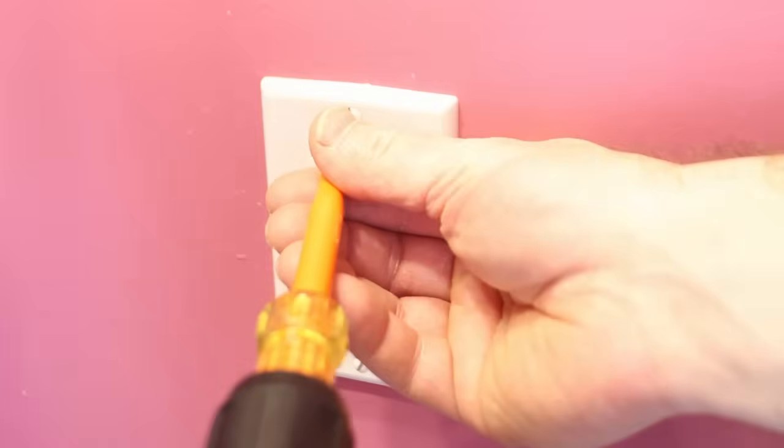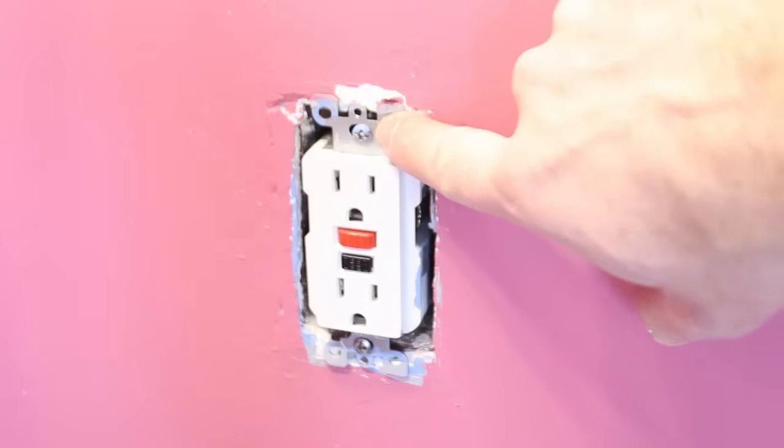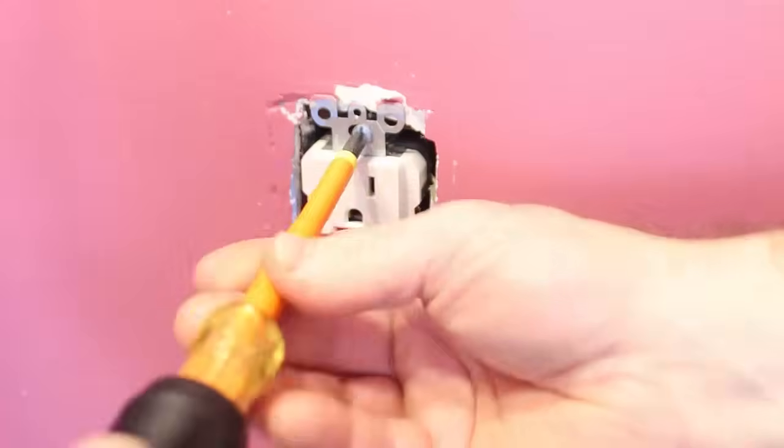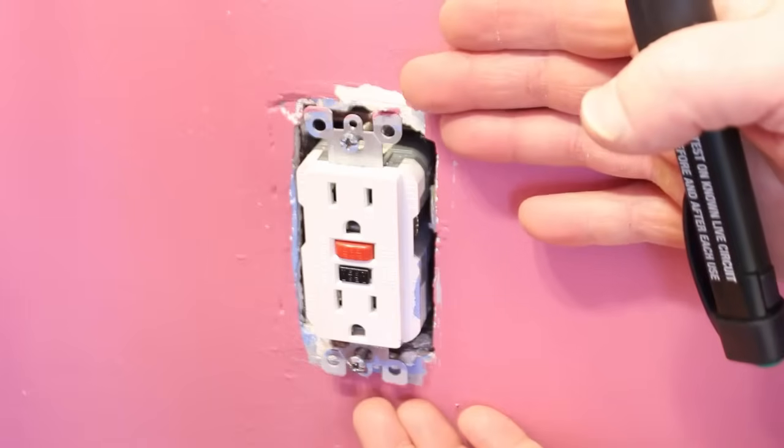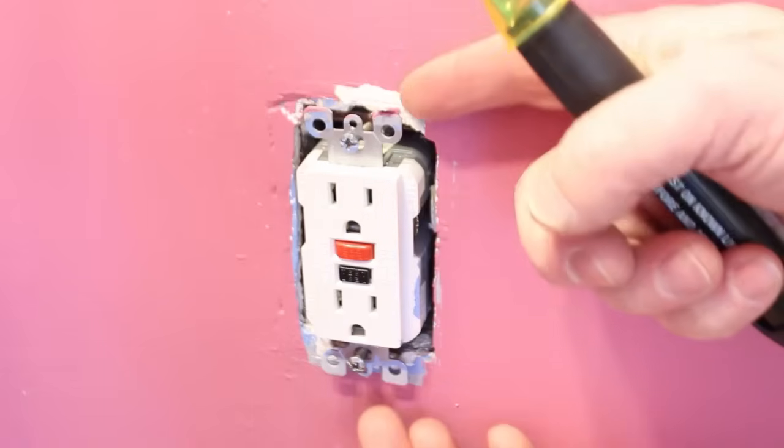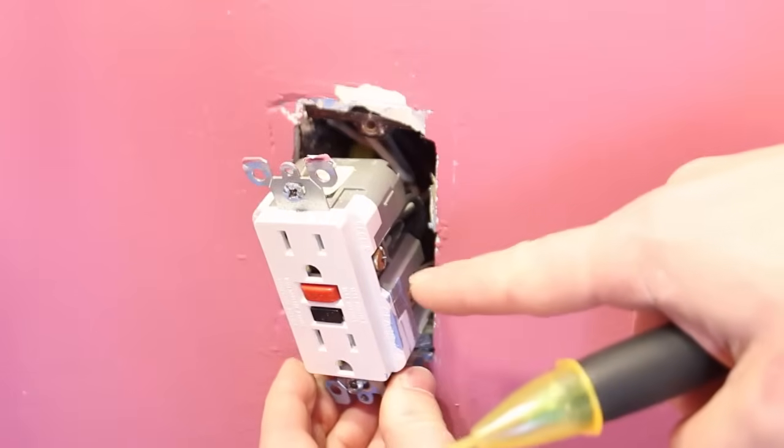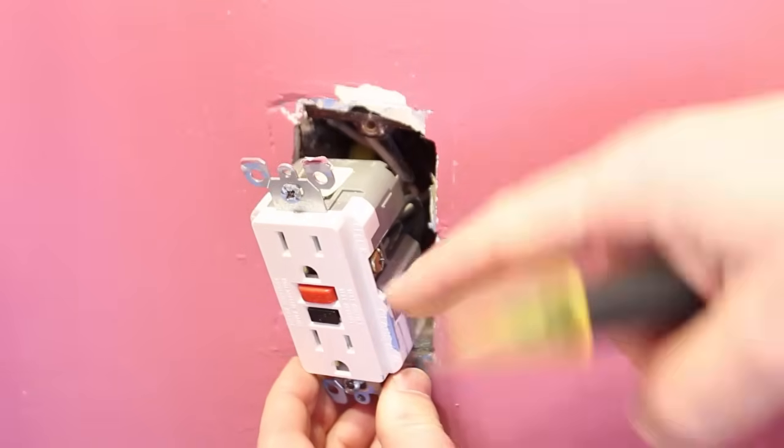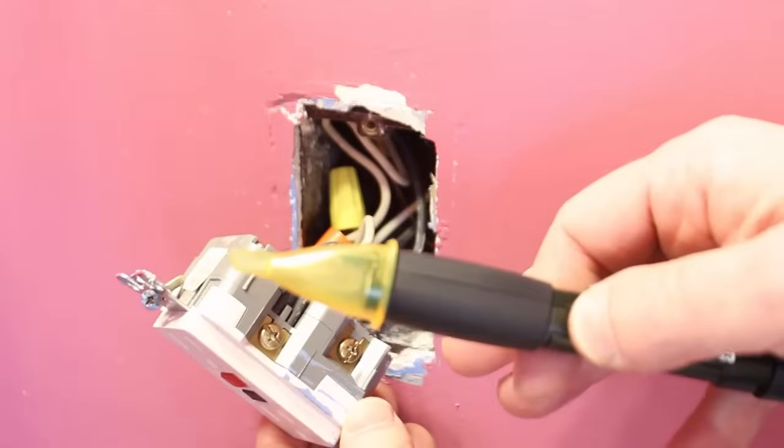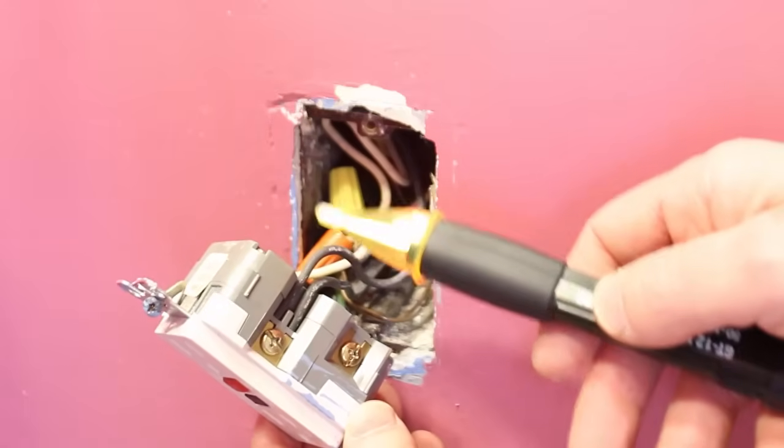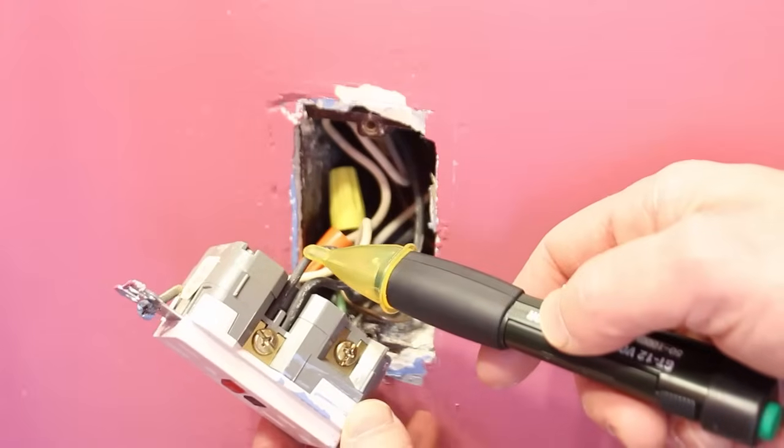Just turn them counterclockwise. Now you can remove the screws that hold the outlet to the electrical box. Again, turn the screws counterclockwise. Now pull the outlet out from the electrical box using the metal tabs. Make sure not to touch the side of the outlet, just in case it's still energized. With your voltage detector, double-check that there's no electricity running to the outlet by placing it on top of the hot wires.